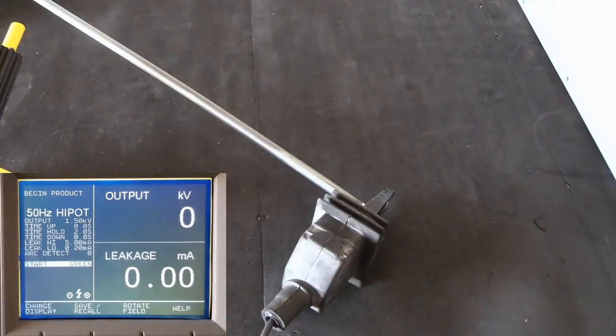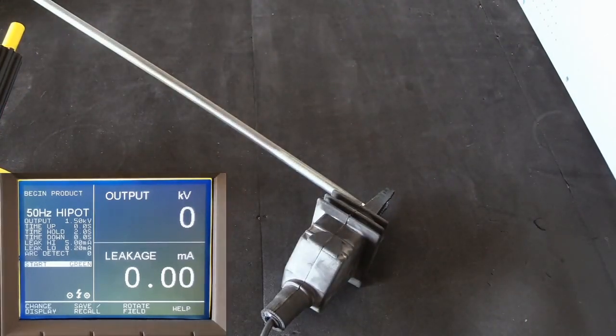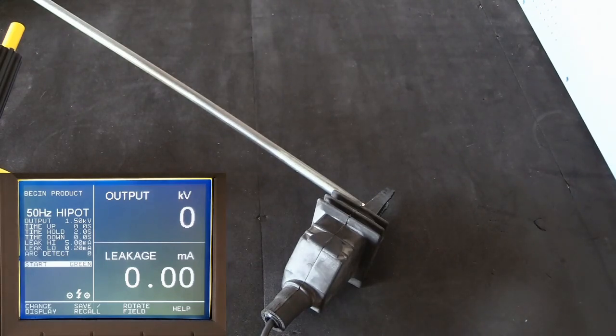So let's quickly talk about the test itself. For this particular test, we're going to apply a voltage of 1.5 kV. We're going to perform that test for 2 seconds. And we've set 2 limits. We've set an upper limit for safety of 5 milliamps, but we've also set a lower limit of 0.2 milliamps in this case. Now that's to catch any potential non-connections.